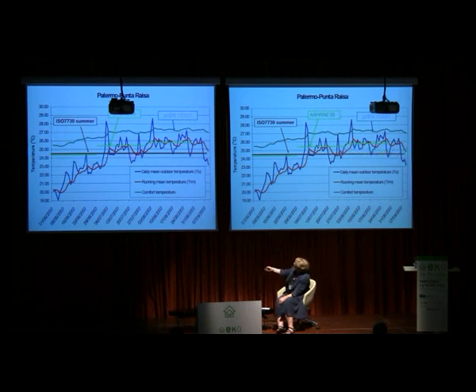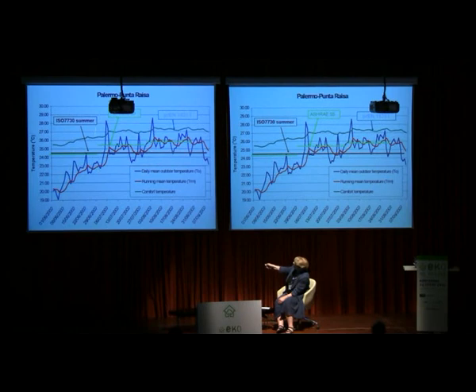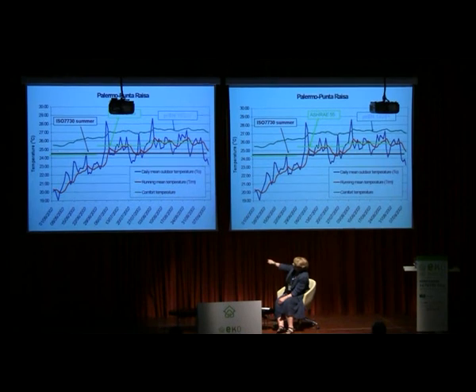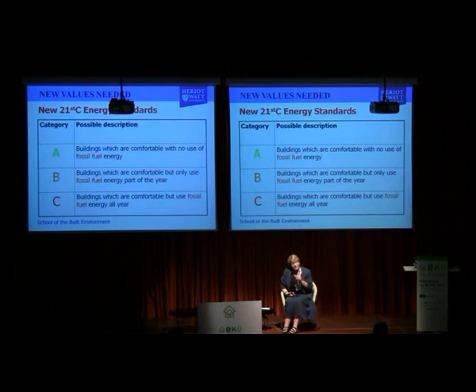But if you take the external mean daily outdoor temperature, as we saw in some of Patrick's work, and the running mean temperature, if you actually use an adaptive comfort algorithm that says you can occupy cooler temperatures in winter and warmer temperatures in summer, just set an adaptive algorithm, even if it's a controlled building. You can open the windows, and you can also probably save, if it's a fixed window building, over 50% of your running costs simply by changing your approach to comfort. So there's a quick win.